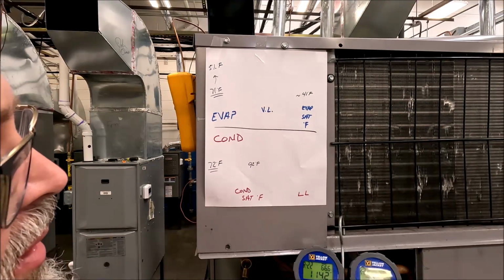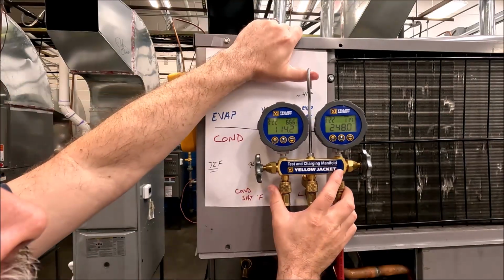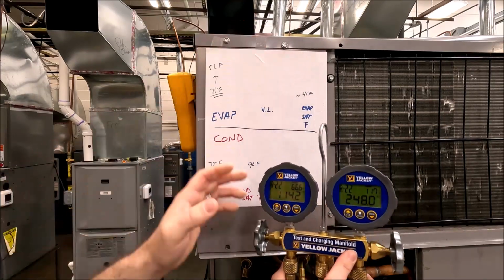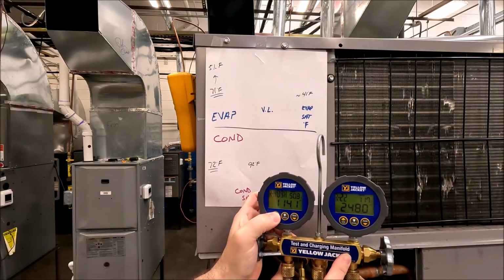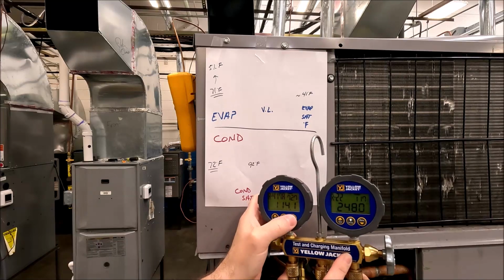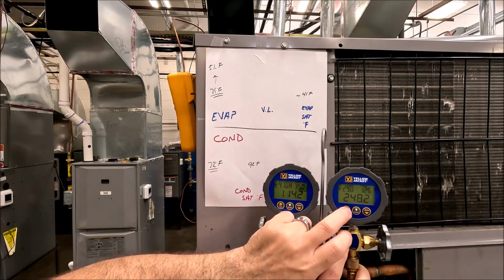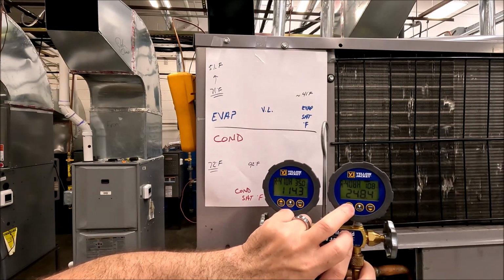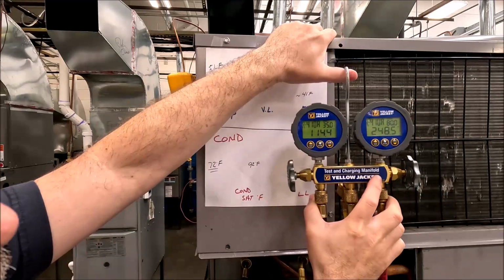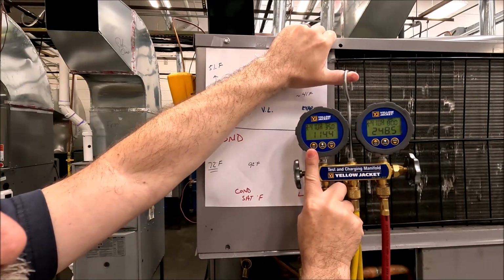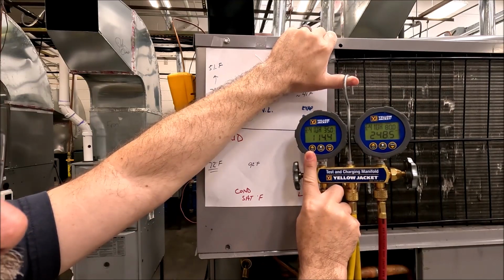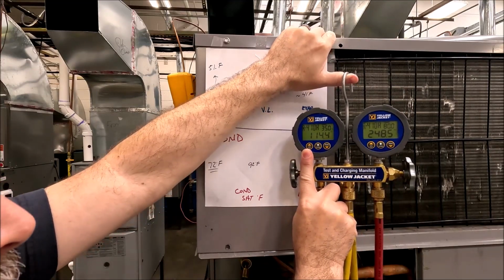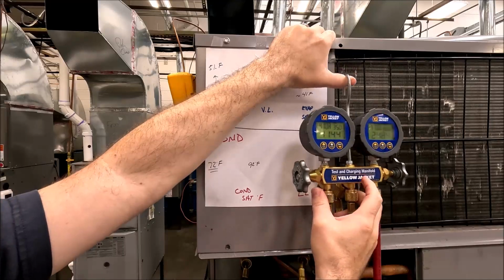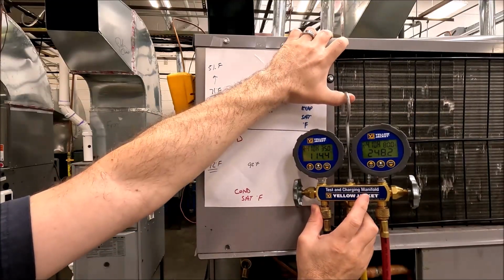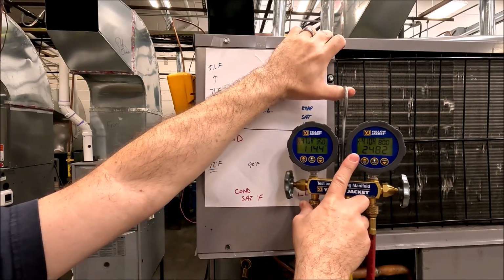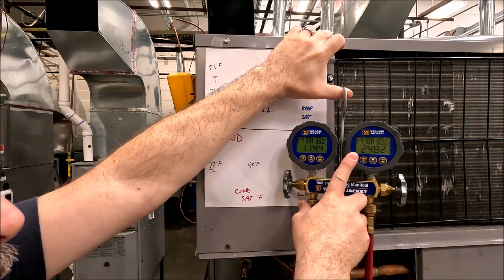All right, so I've got my gauges here, and it went back to R22. These are nice little Yellow Jacket gauges, but when they reset, they go off, all right? So I'm looking at 114.4 PSI and about a 35 degree coil, saturation point, that is. And on my high side, I've got 248 PSI and about an 80 degree coil.